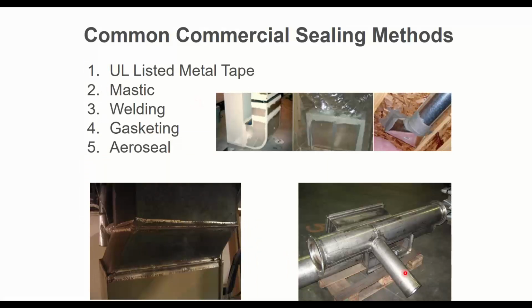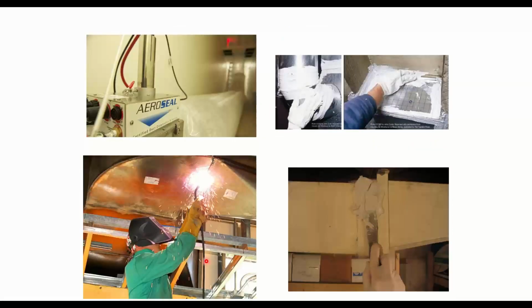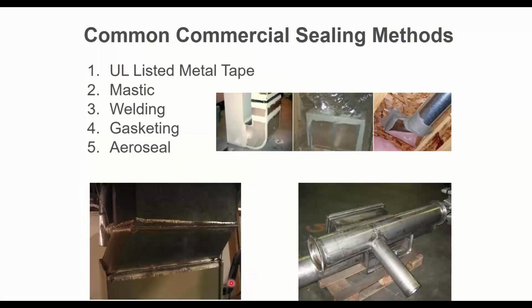But you can use mastic. You can weld the duct, right? That's not very common. Most people are not going to weld ducts. A regular office building or a school, you're not doing that. But if you had a laboratory or something like that, and you really could not have any possible leakage on the exhaust side of the system, because whatever you're exhausting out is hazardous, then perhaps you would choose to weld the ductwork.